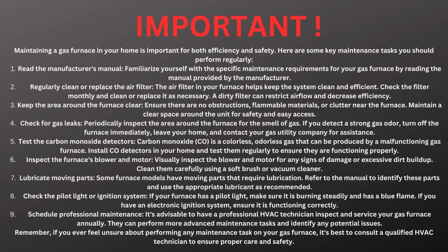Inspect the furnace, blower motor, and its motor settings. Visually inspect the blower and its motor for any signs of damage or excessive dirt buildup. Clean them carefully. If you learn to take the panels off, you can take the hose off of your vacuum cleaner, use one that has a little brush connection, and go in there and clean the walls and the sides.